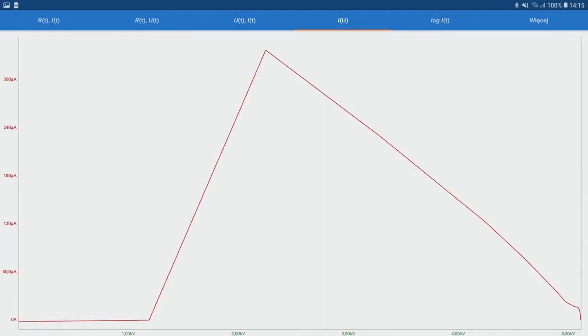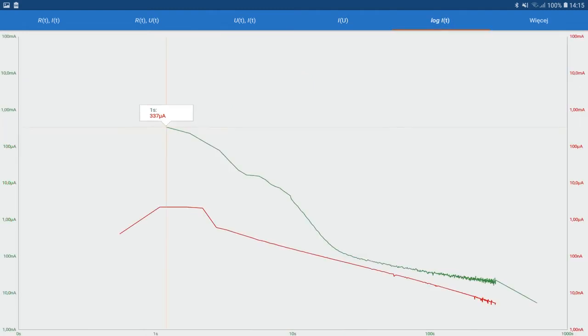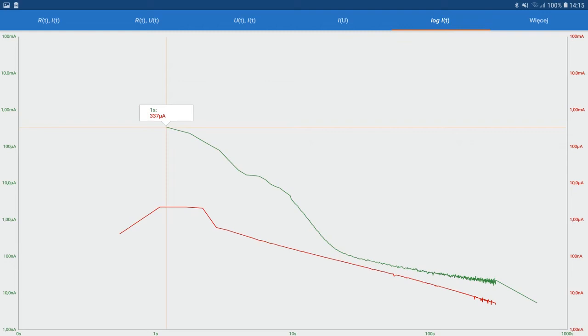The fourth is the waveform current versus voltage diagram. The fifth is logarithmic current in the time graph, and in the first and the third graphs of the current, we do not see anything interesting, we can see only peak of the current during the polarization, and almost zero in the end of the graph. And that's why we have this plot of the logarithmic scale. And here you can see the polarization and depolarization currents, the shape of the graphs, and basically how this shape change over the time, gives us information about what happening with the isolation.